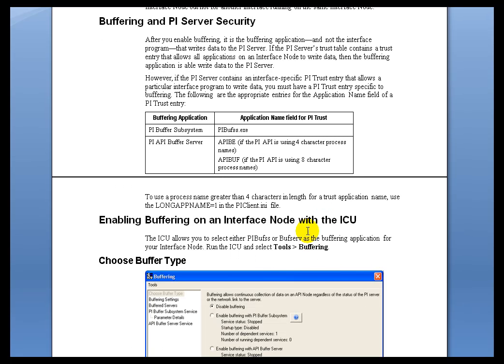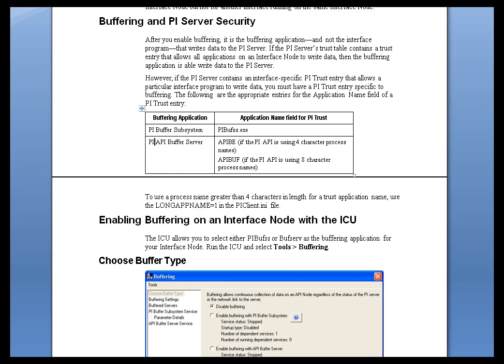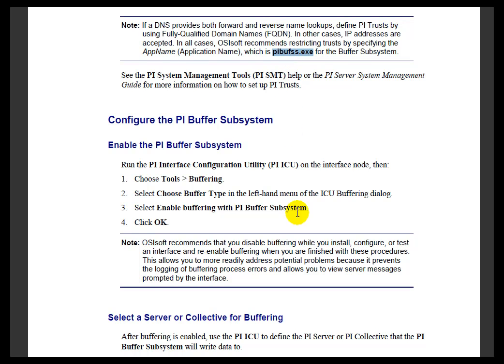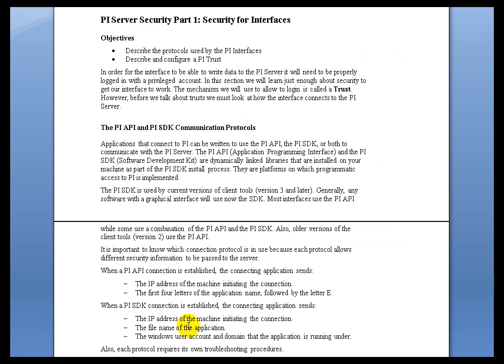I'm looking at the OPC Interface here. It's telling me for the Buffering Subsystem, it's PIBuffSS. If you look in the Buffering documentation itself, we mentioned PIBuffSS.exe. So if you're not sure yourself what the actual Executable is for Buffering or whatever application that's unattended that is SDK-based, just take a look in the documentation, see if you can find it in there.